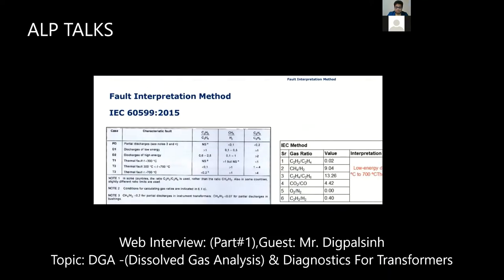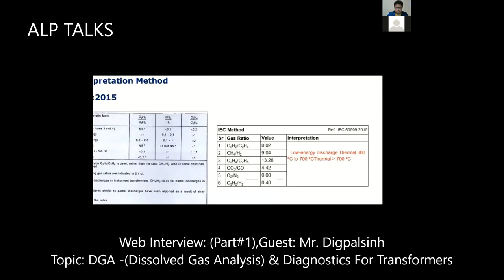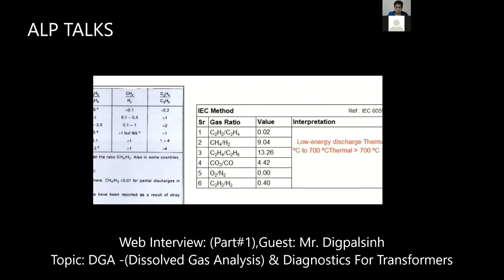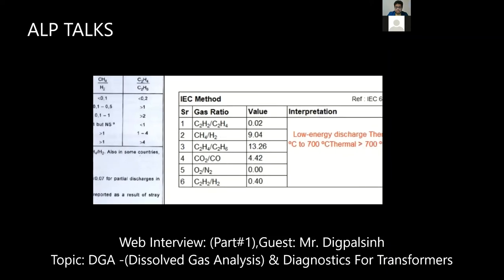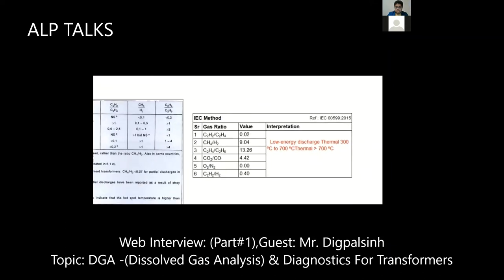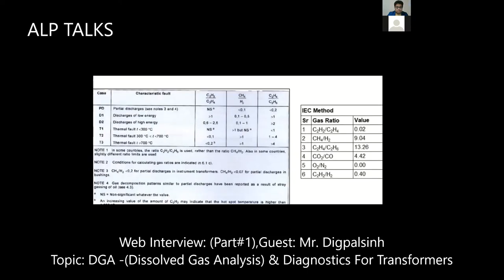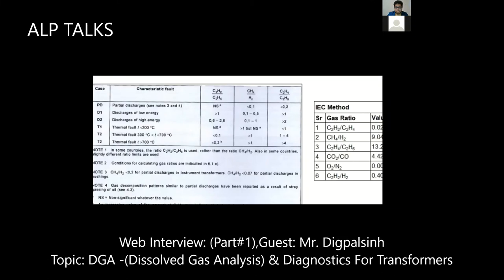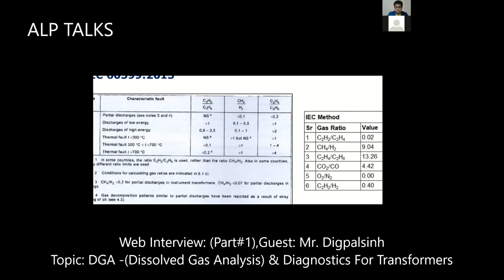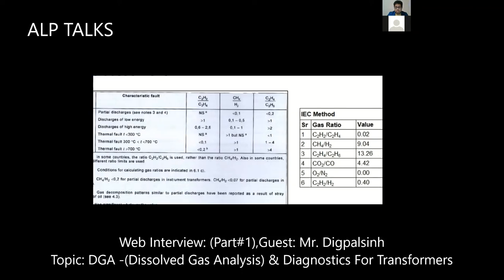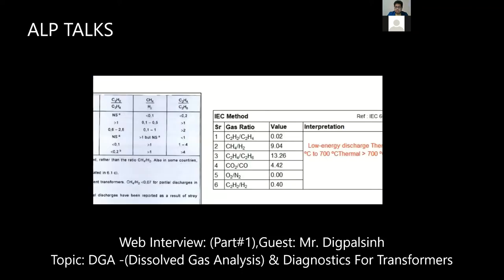Here I have done some analysis and calculated the ratios, and in that I have found low energy discharge and thermal fault. This ratio comes for D1 and thermal fault. It is greater than 700, T3. So when I calculate this value, if we check discharge of low energy, the first ratio C2H2/C2H4 is 0.02.